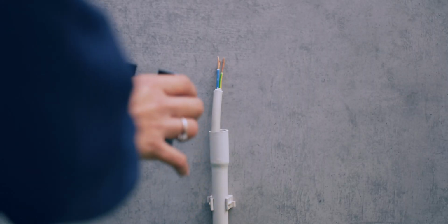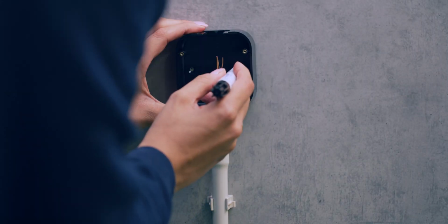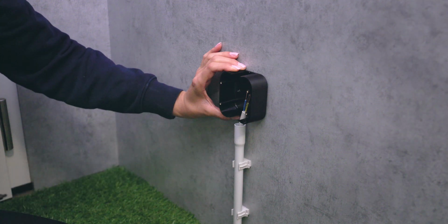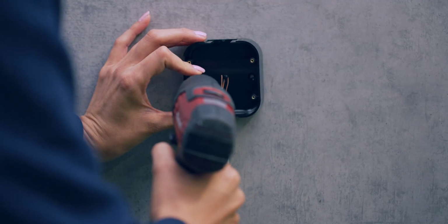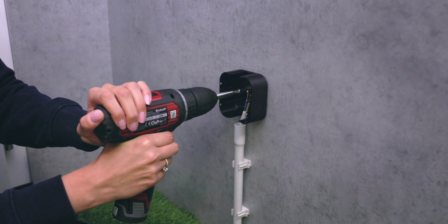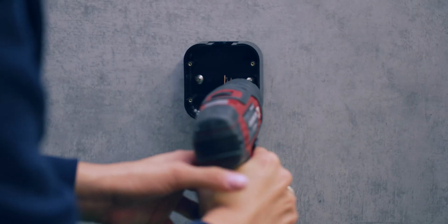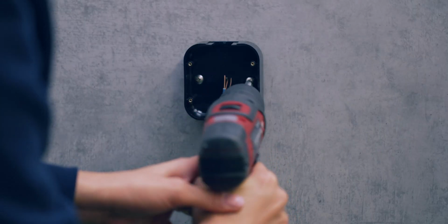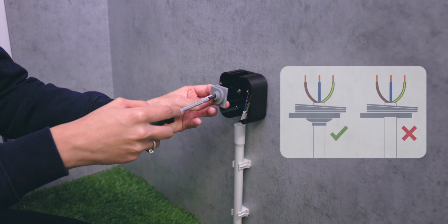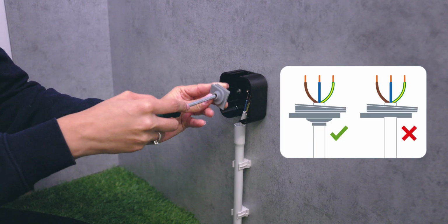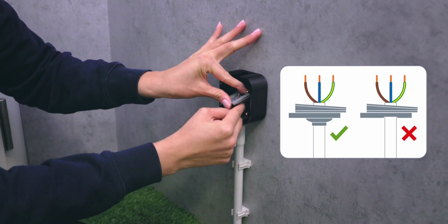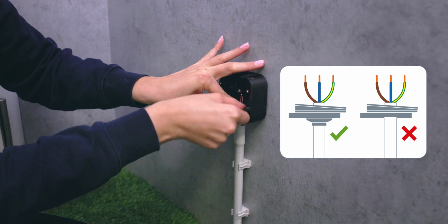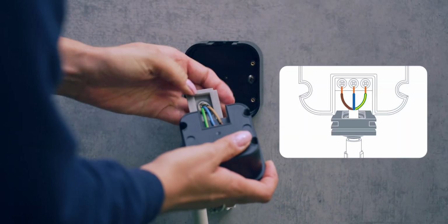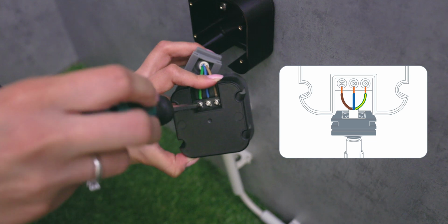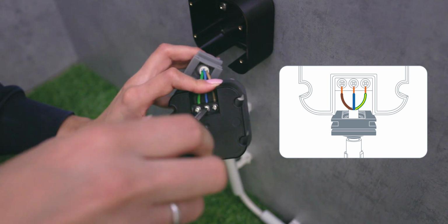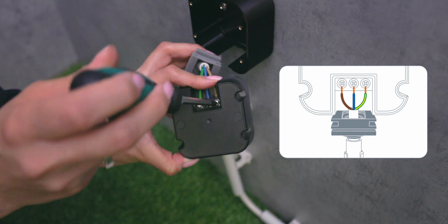Take the mounting frame and position it in your ideal location and mark the screw holes on the wall. Next, drill into your markings with screws ideal for your wall type. Then secure the mounting frame with suitable fastening material, such as the supplied plugs and screws for stone and concrete. Run the stripped wires through the rubber cap with the embossed membrane. Attach the wires to the corresponding terminals. Now, tighten the screws and be sure to check the tightness of the wires.